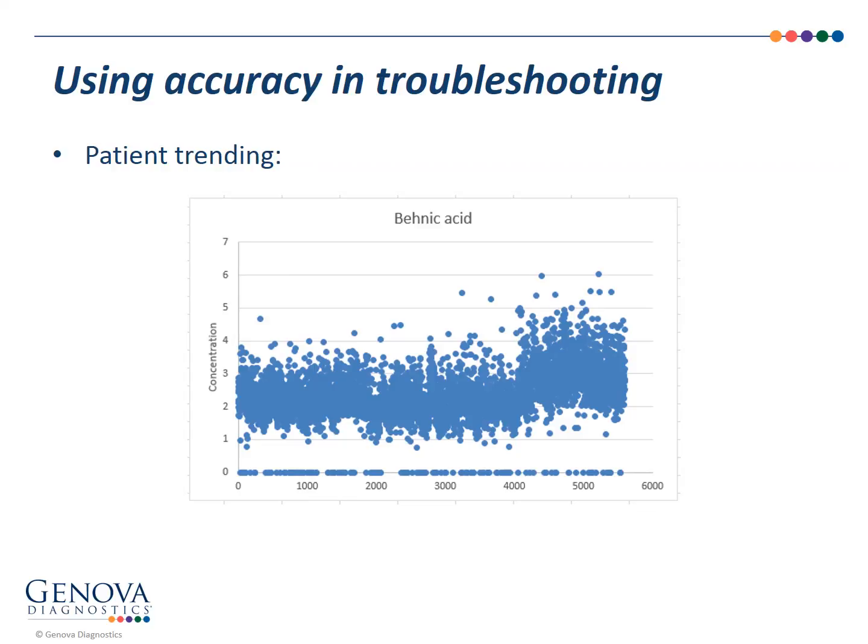Now, it's an interesting story. This particular analyte is part of our EMFA assay, our essential metabolic fatty acids. So these are a lot of your good fats, and it's typically a pretty well-behaved assay. One time when I was supervisor over this area, the tech brought me a batch and he said, this batch just looks really funny. It looked something like this for a number of the analytes. All the patients in that batch had shifted. We said, well, that's strange, it doesn't usually do that. We went back to the instrument and checked the calibration curves and they were pretty and the peaks were pretty. But the key point was that the controls were right where they were supposed to be.